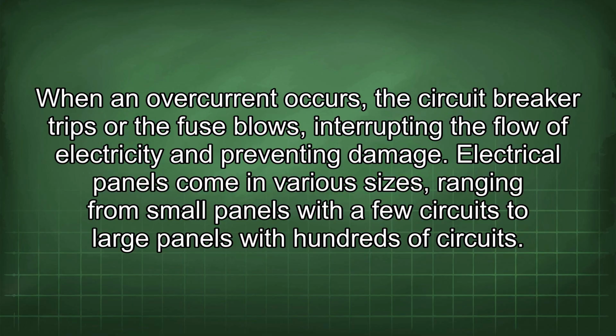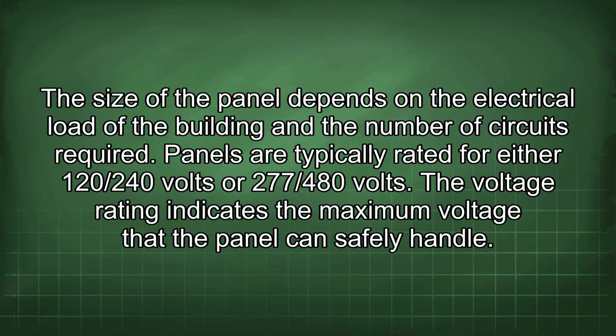Electrical panels come in various sizes, ranging from small panels with a few circuits to large panels with hundreds of circuits. The size of the panel depends on the electrical load of the building and the number of circuits required. Panels are typically rated for either 120/240 volts or 277/480 volts. The voltage rating indicates the maximum voltage that the panel can safely handle.